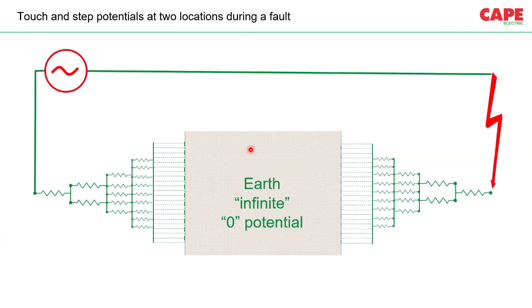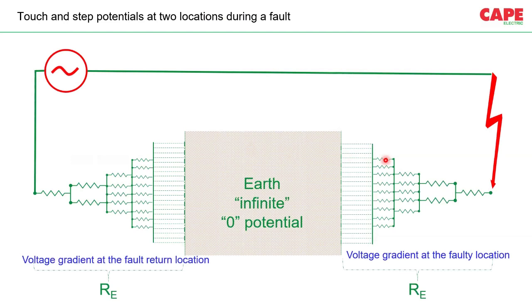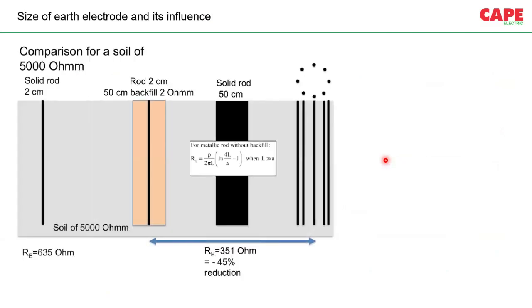What you should also understand is, in case of a fault, this voltage gradient will be created at two places. One is at the place where the fault is happening, and the second one is the place where the fault is returning back to the source. Two earth electrodes are there. As a result, at both places a voltage gradient will be created. Another misinterpretation, anyhow, this is also not a part of our presentation, but still for the explanation, because a lot of times people ask about chemical earth and its applicability. Now, we made a webinar about 4 or 5 months back. You can go to our link and look at the video, where these are very well explained.